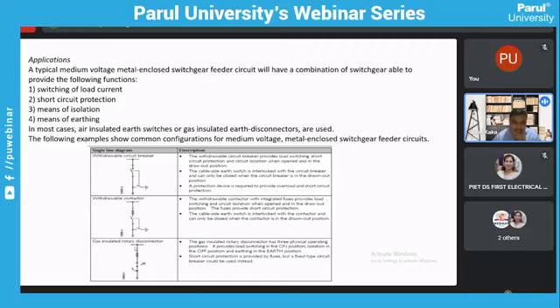Again, as we know, fuses will come into the picture only during short circuit cases, and normally motor protection relays (MPRs) are used to cater for motor thermal overload, negative sequence, and a whole bunch of protections associated with the motor. So that is something separate which the motor protection relay will be taking care of. Also, careful coordination in terms of the thermal capacity, or configuring the thermal protection of the motor, is something that needs to be designed carefully so that we do not allow the motor to exhaust its thermal capacity.